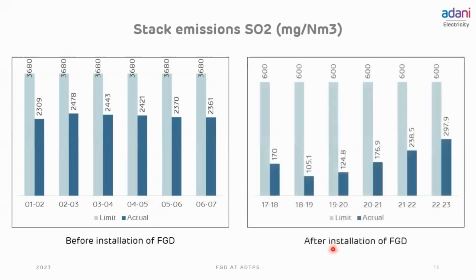After we installed the flue gas desulfurization system, I have shown you the last 6 years of SO2 values. The limit given by the Ministry of Environment and Forest for this thermal power plant is 600 milligram per nm cube, and we are achieving around 200 continuously. So we can see how much difference there is, and the good environmental performance of this power plant.